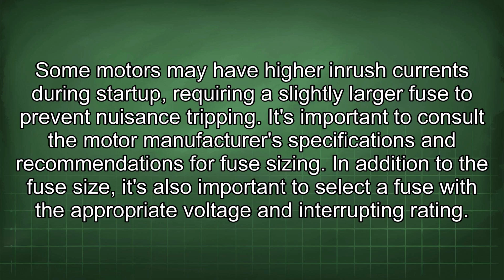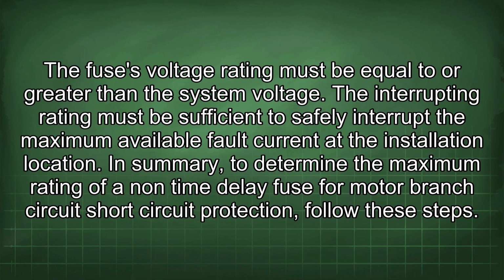In addition to the fuse size, it's also important to select a fuse with the appropriate voltage and interrupting rating. The fuse's voltage rating must be equal to or greater than the system voltage. The interrupting rating must be sufficient to safely interrupt the maximum available fault current at the installation location.